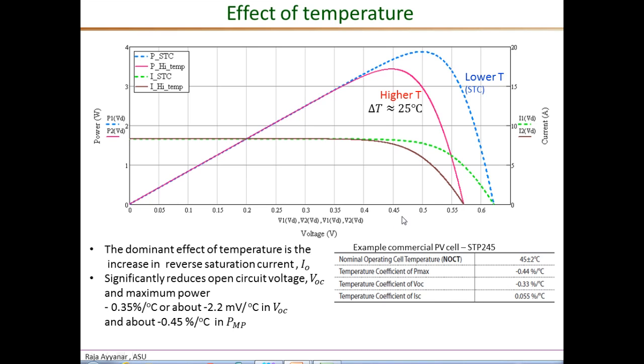In this example, corresponding to a 25°C rise in temperature, the power comes down by 0.44 × 25 = 11%. So the power is reduced by roughly 11%, going from about 3.95 watts at STC conditions to about 3.5 watts at the higher temperature.